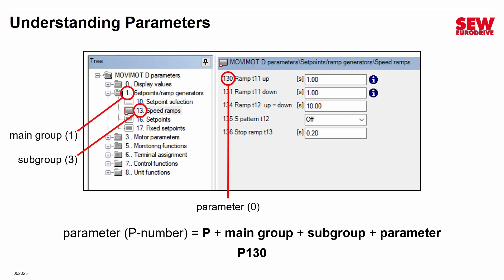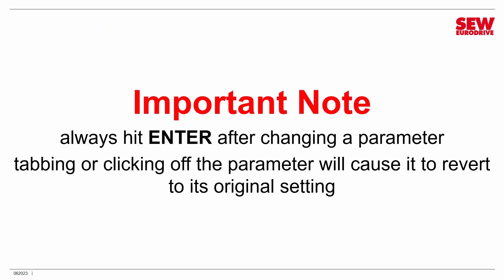So if somebody tells you to go to a particular parameter, take the first digit — that points you to the group. The second points you to the subgroup within that group, and the third points you to the individual parameter. Not too complicated. Also, whenever you're changing parameters, you must always hit Enter after changing a parameter. If you tab or click off to another parameter, the change will not stick and the parameter will revert to its original setting. That's true with almost all SEW EuroDrive software products.